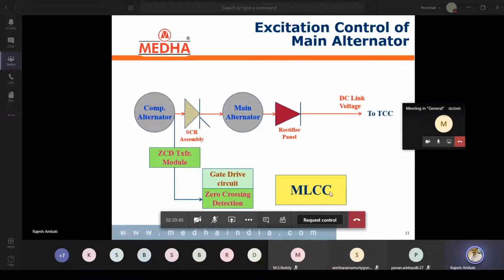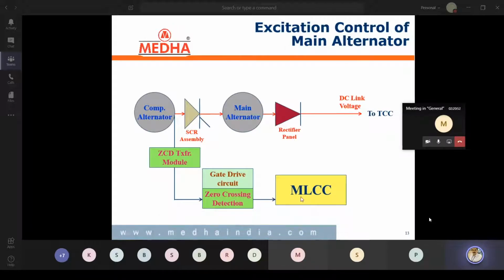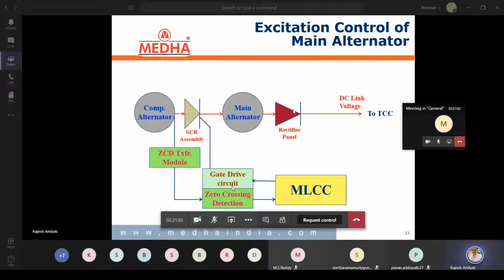First, MLCC has to monitor the zero crossing point of each phase. Separately, each phase of the 3-phase signals will come to MLCC. Then MLCC calculates when each phase has to be triggered. For that purpose, it generates a 5-volt signal. In this gate drive section, that 5-volt signal converts into 12 volts, and those 12-volt signals go to the SCR gate, and accordingly it triggers, and that AC converts into the required DC.